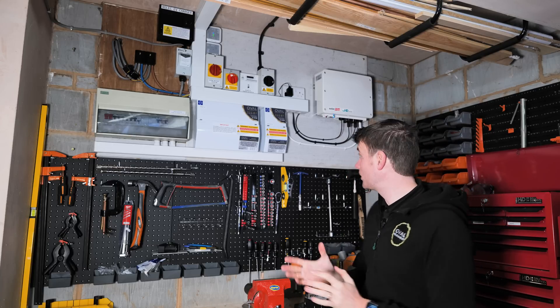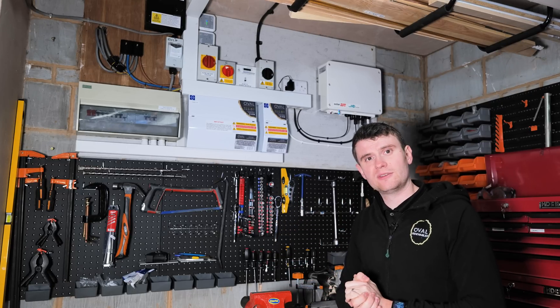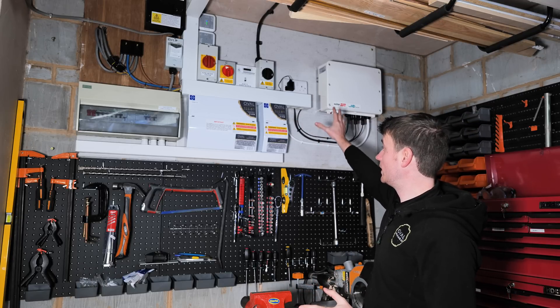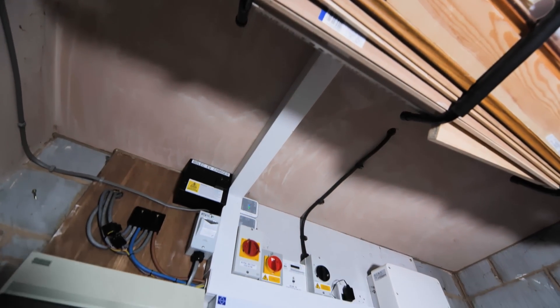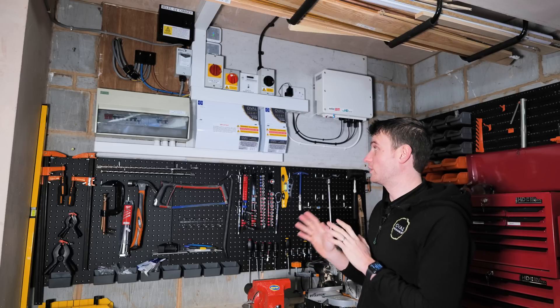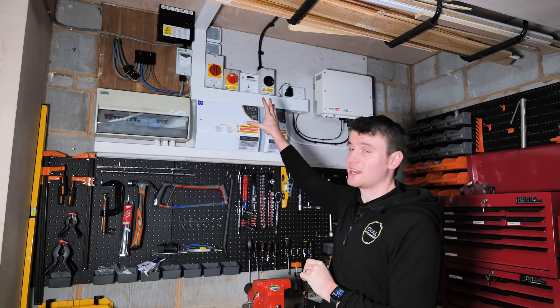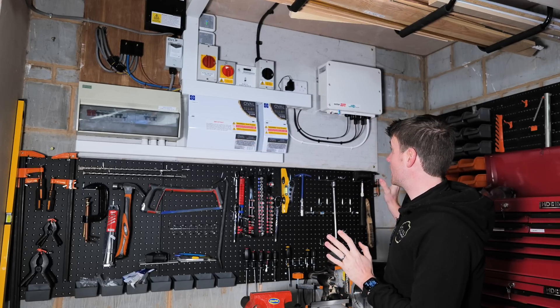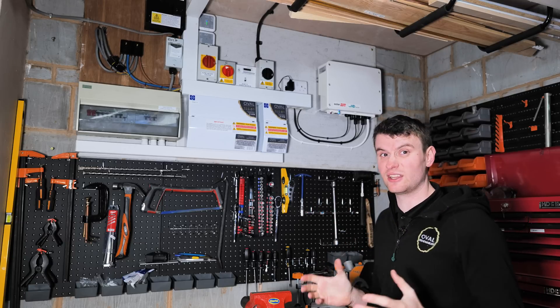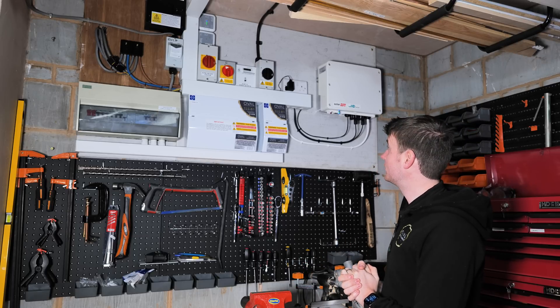I'm really pleased how this one turned out because the customer's obviously got a bit of a workshop here and she didn't want any of the workspace taken up if we could help it. That's why we've put everything up out the way on this wall here. You can see we've got our fire board — 12mm Hardie backer board, which is a cementitious board that has been fire tested and is heat resistant. We split the tails using some Henley blocks just there — that's how we've got the power to our board. The customer doesn't have to worry about it getting dirty from any of their workings because it's up out the way, it's not going to get bashed or knocked.